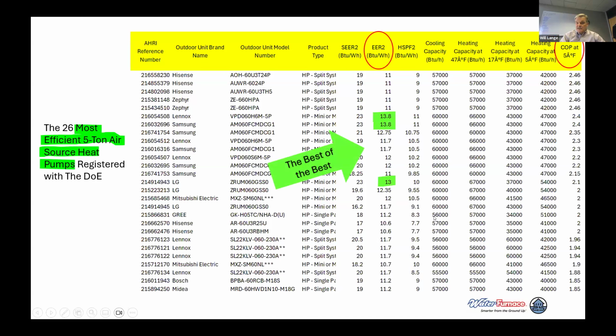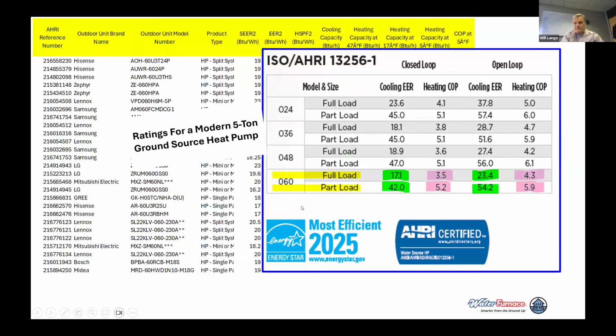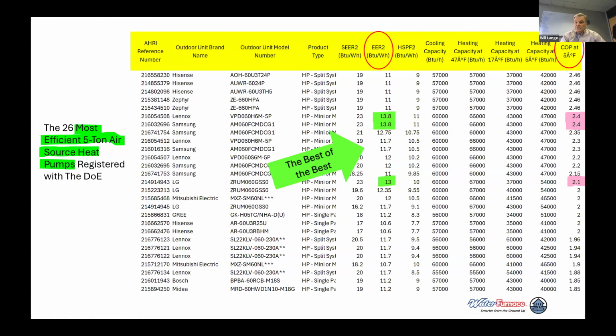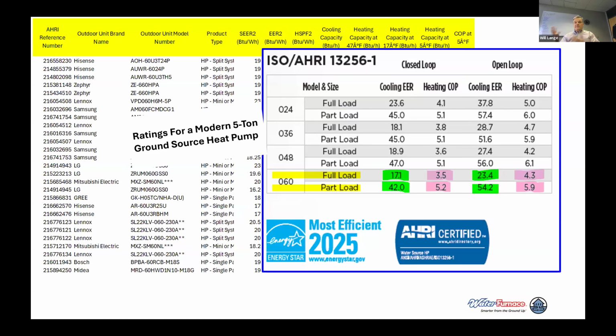Remember, these are the best of the best. And in green, I've highlighted the best EERs out there among the best, and the COPs that go with them. So kind of memorize those numbers if you can. 13-ish for the EER. This is that ground source heat pump I showed you a picture of a few minutes ago. These are the COPs and EERs related to that unit. And you can see that it goes as high as 54 and as low as, worst case scenario, 17. And if you think back, we were talking 13.8 for the best of the best of the best in the 5-ton category. So extreme efficiency as a result of being ground source.